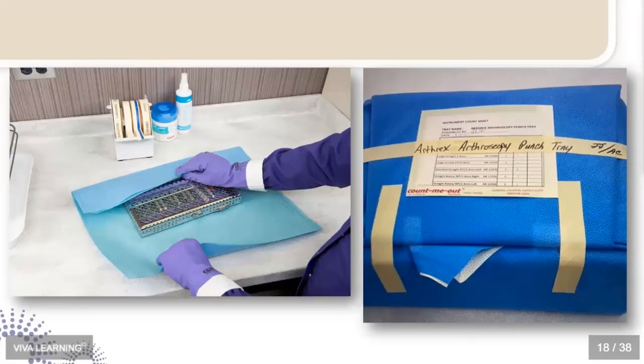Also, you see that they wrote on the tape, never ever write on the cassette, on the sterilization wrap fabric itself. It's not validated to be written on. You would never write on the paper of a pouch, because remember, those pores open and close, and if you've got ink on there, it can compromise that integrity. So you only write on the laminate of the pouch, and you only write on the tape of a wrapped cassette. And also, we have to use validated steam sterilization tape. Just because masking tape looks like sterilization tape, it's not been validated for use. Obviously considered off-label use.